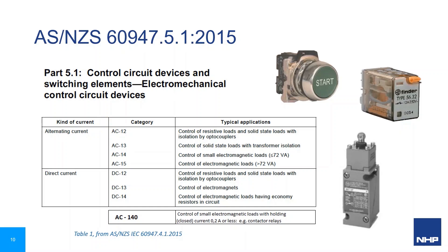The product standard for control circuit devices is IEC 60947 part 5, with utilisation categories and switching capabilities for push buttons, control relays, limit and position switches defined in part 5.1. AC-140 is an additional utilisation category with low current values for proximity switches from part 5.2. Solid state relays themselves are defined in IEC 62314.